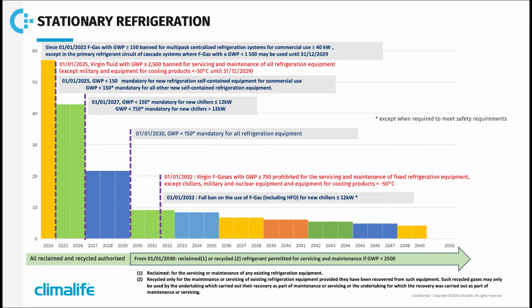The second point of the F-Gas concerns bans. If you look at the top of the screen, we have since 1st January 2022 the obligation to no longer use refrigerants with GWP of 150 or more in new centralized installations of more than 40 kilowatts, and only refrigerants with GWP less than 1500 in the primary circuit of a cascade system. This point existed in the previous F-Gas. We also see that tomorrow, on 1st of January 25, all refrigerants with a GWP over 2500 will be forbidden for maintenance, excluding what you can read on the screen.